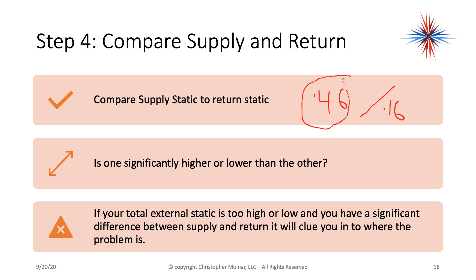In this case, the blower is pulling a very high suction pressure but not putting much into the supply duct work. If you don't find anything wrong with the return, you will have to look at the supply, because it could have a big gaping hole in the supply duct. But not with those temperature splits we saw — the temperature split is too high, not enough air flow.